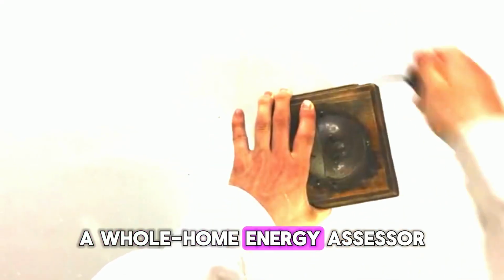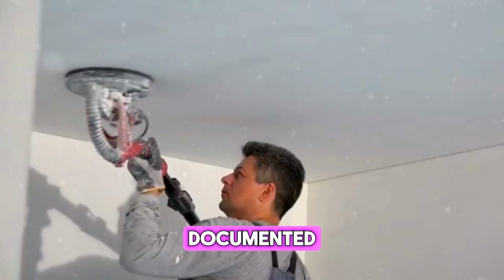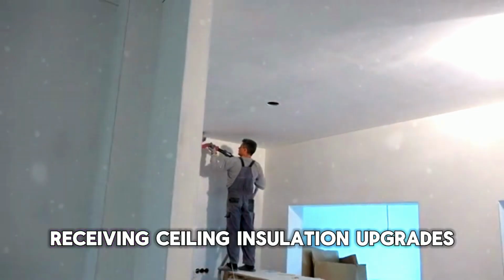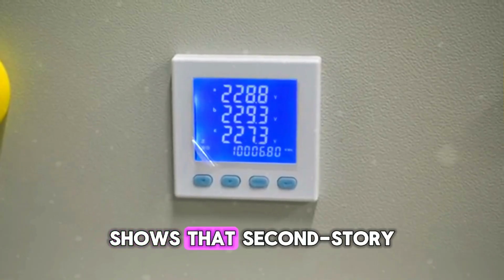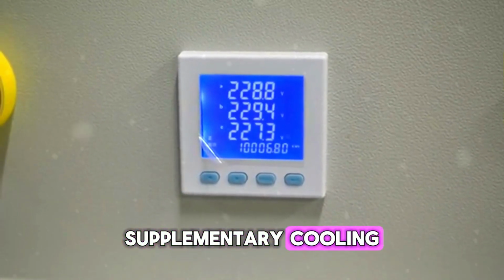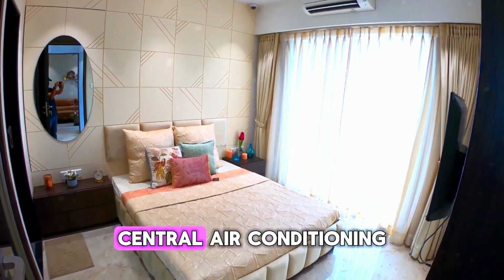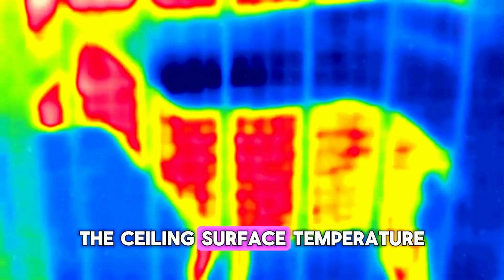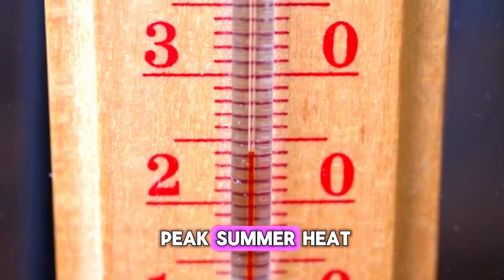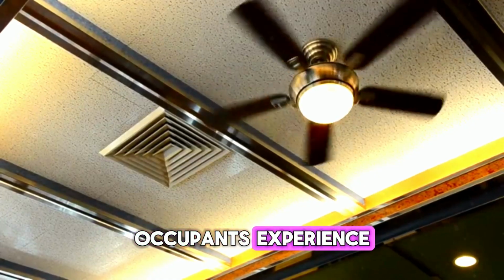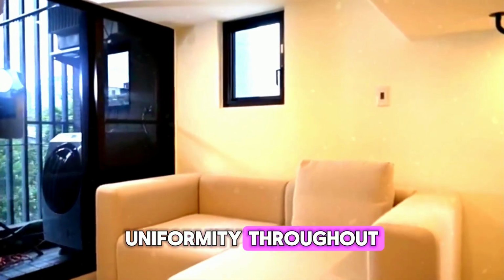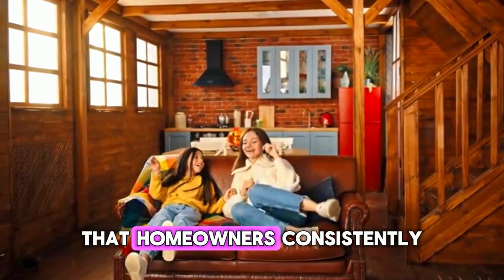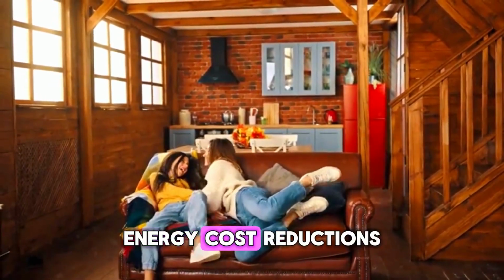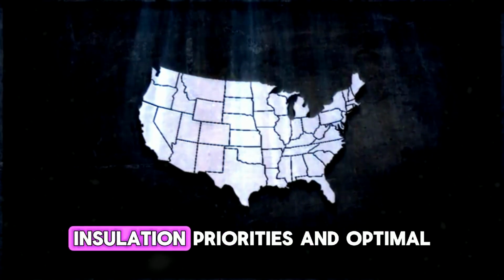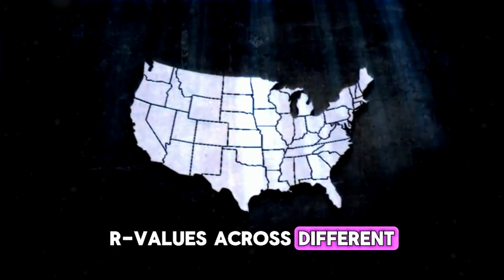Patricia Donnelly, a whole home energy assessor operating across the Mid-Atlantic states, has documented comfort transformation patterns in homes receiving ceiling insulation upgrades. Her client tracking shows that second-story bedrooms that previously required supplementary cooling during summer nights returned to comfortable temperatures using normal central air conditioning following insulation upgrades. The ceiling surface temperature differences between uninsulated and R60 conditions reach 15 to 25 degrees during peak summer heat, eliminating the radiant discomfort that occupants experience beneath hot ceilings. The improved temperature uniformity throughout the upper floors represents a quality-of-life benefit that homeowners consistently report as equally valuable as the energy cost reductions.